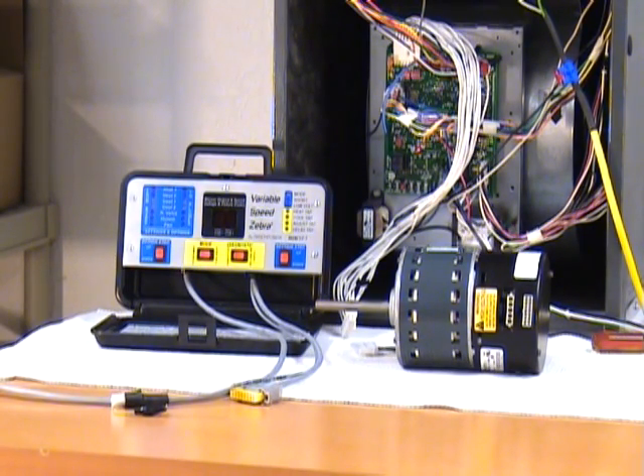Instead of just plugging into one of the motor connectors, as that other tool does, the variable speed zebra is inserted in line, in between the furnace, air handler's control board, and the motor's electronic package. It plugs into the existing 16-pin connectors, one male and one female, and is ready to begin its analysis immediately.